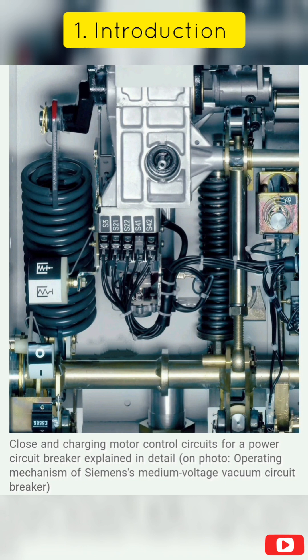While the protective relay in medium voltage applications requires control power, the typical medium voltage breaker is closed and opened via mechanical springs in the breaker, and there is a manual close and trip button on the face of the breaker along with a flag indicating breaker status. The operating mechanism is a stored energy mechanism. The closing spring is charged either electrically or manually. It latches tight at the end of the charging process and serves as an energy store. The force is transmitted from the operating mechanism to the pole assemblies via operating levers.